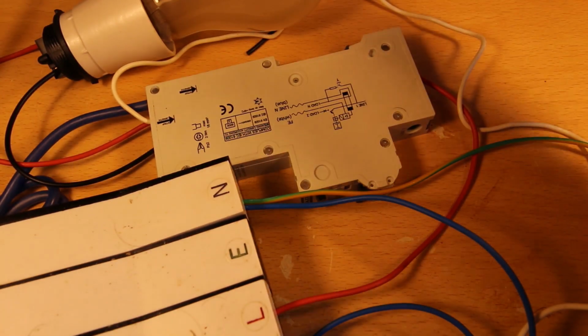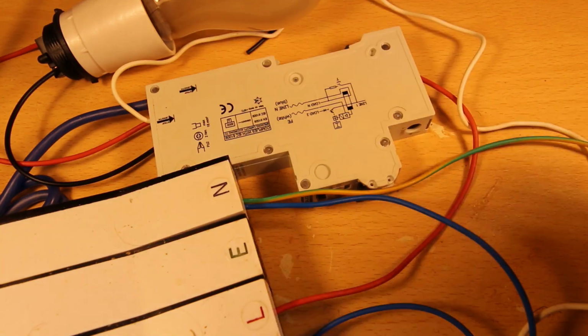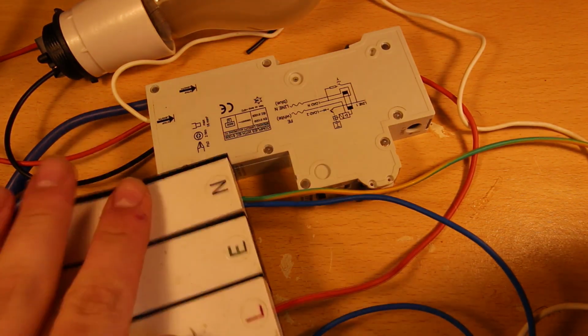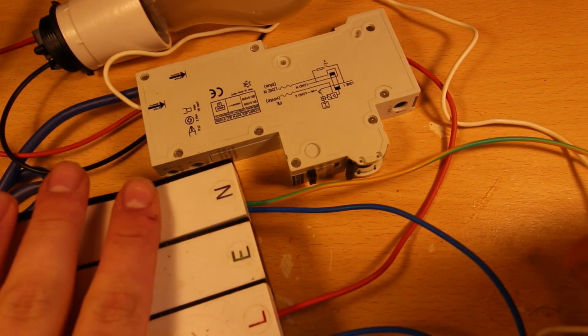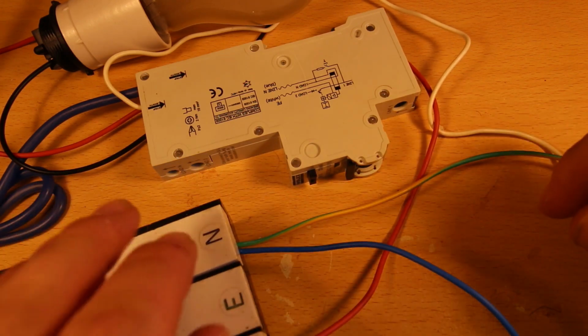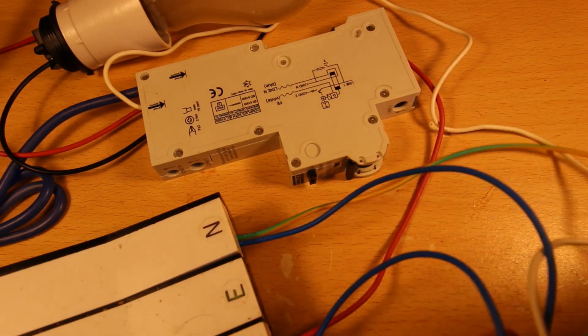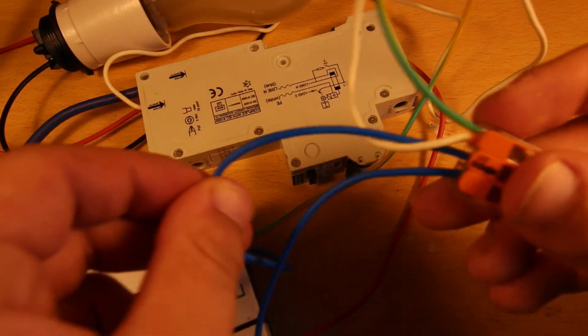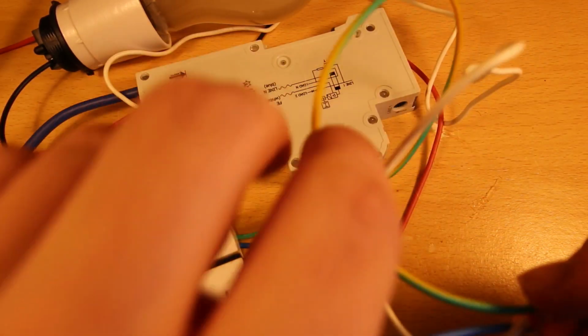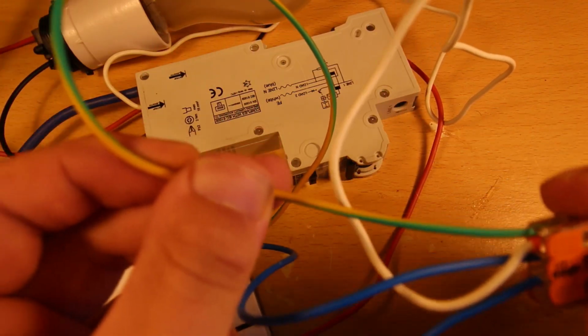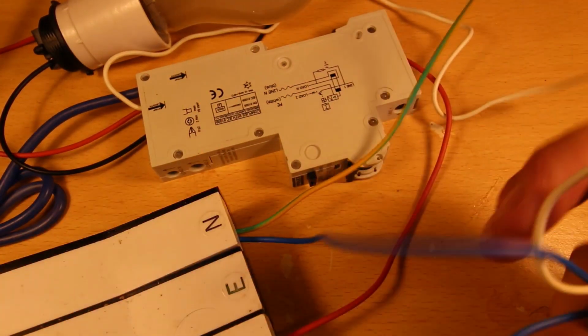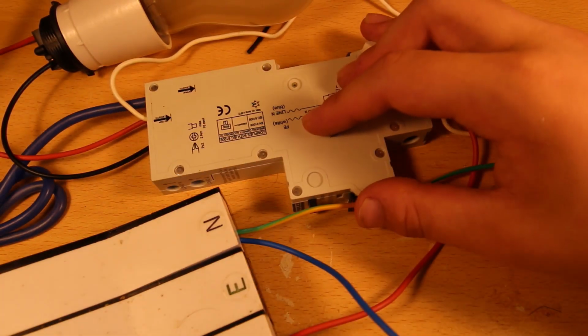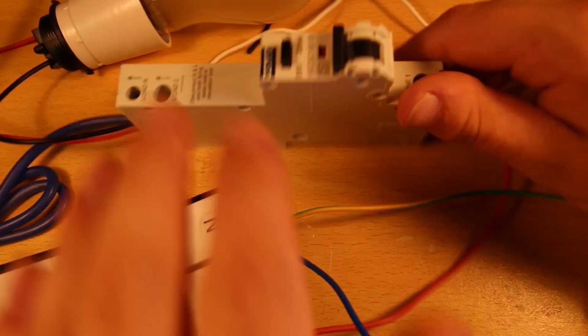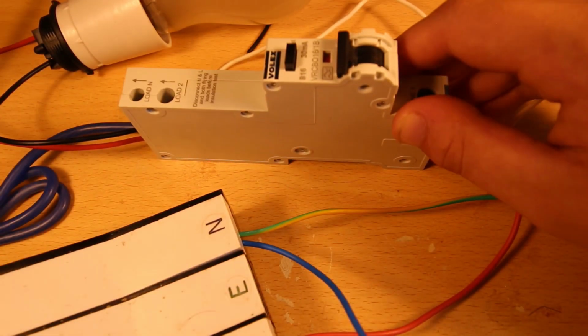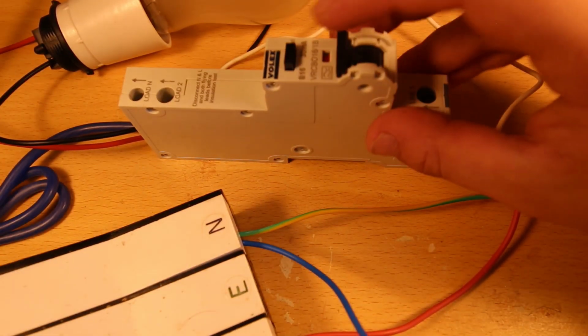So this is my setup here. It is a bit of a rat's nest, but I will explain what we have. The quick connect here is my pseudo grid supply. I have, coming from the neutral here, because I don't want to trip the RCDs in the house, my pseudo PEN, and this is my basically diverted neutral alternative path. This white one is the functional earth for the RCBO, because that's what I had on hand. This is basically just an RCD but with an overcurrent protection rating on it too.